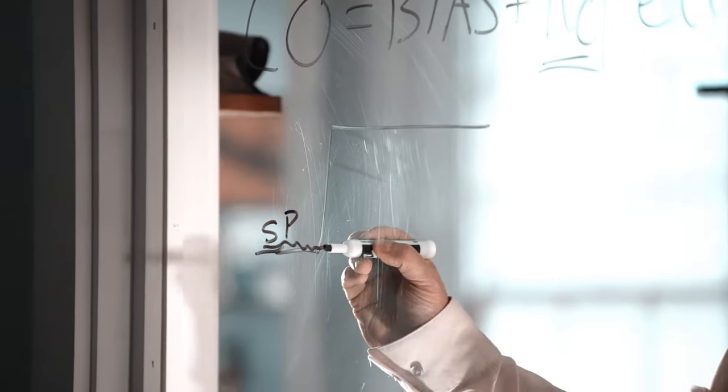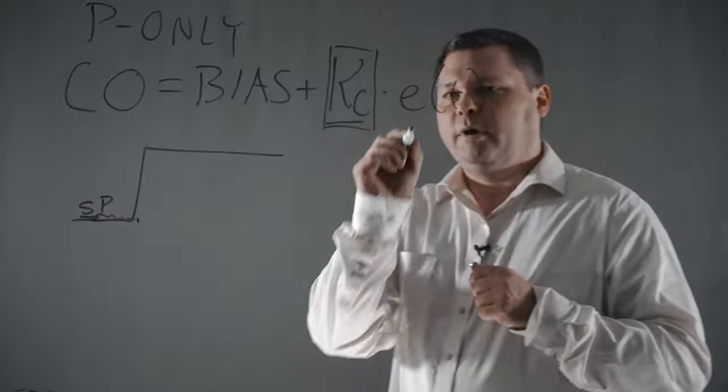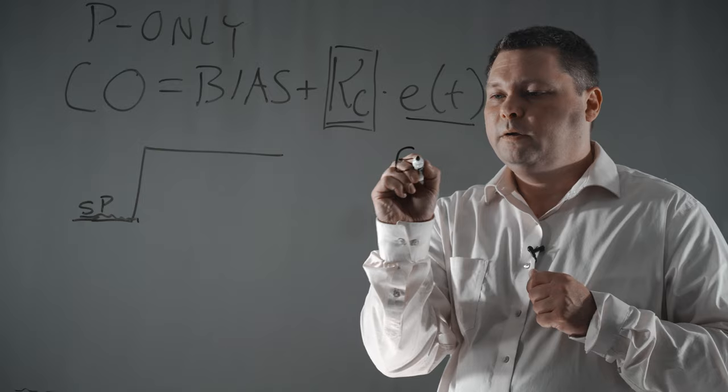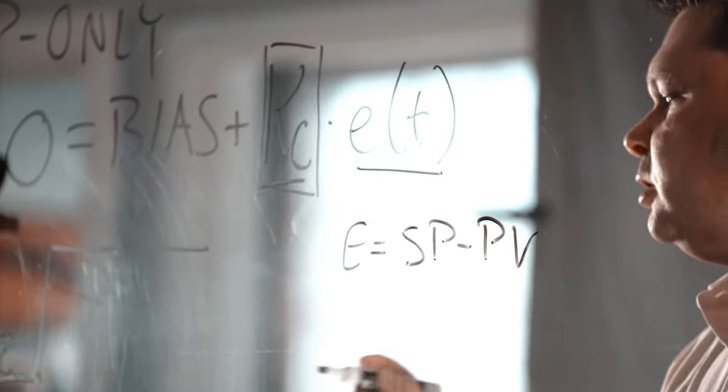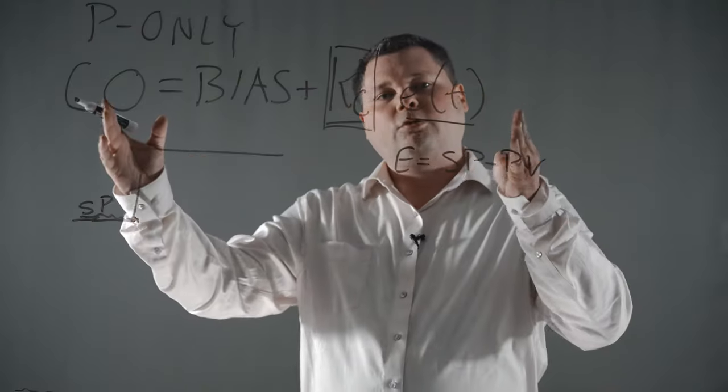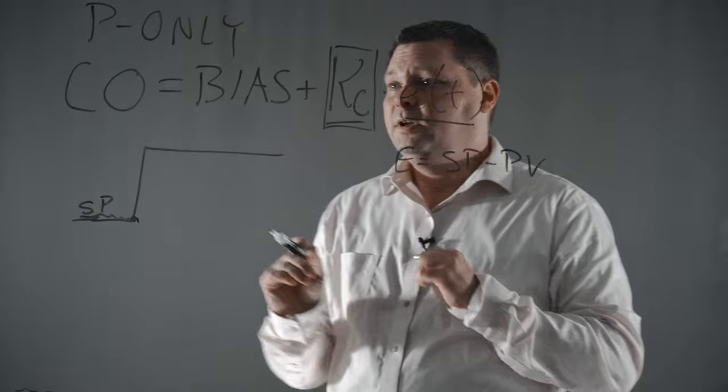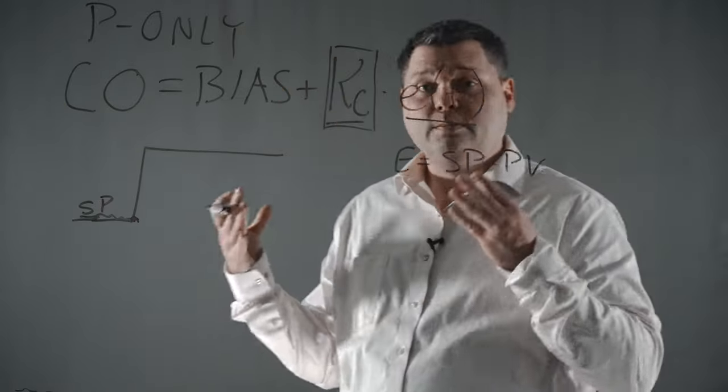So if we start with a setpoint change, so this is our setpoint, and our process variable starts down here, we have essentially no error. This error term, this portion of our equation, is error is equal to the setpoint minus the measurement. So at this moment right here, we have no error. So if you think about what this equation represents, when we have no error, this term over here on the right drops to nothing. And all we're left with is the controller output is equal to the bias value, or the starting position.